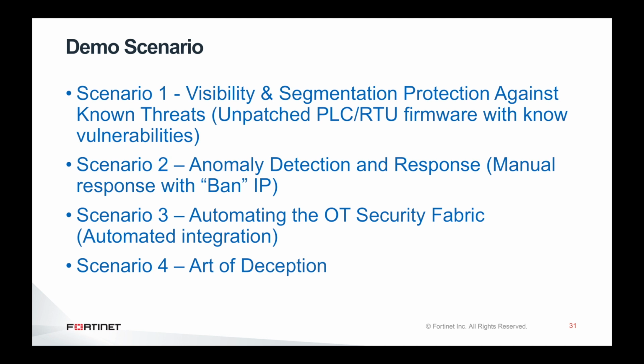Now, the use case here is virtual patching. So what is virtual patching? In most ICS environments, PLC and RTU are running legacy firmware which has known vulnerabilities with CVEs reported against this firmware. As plant managers do not want to disrupt production, these PLC and RTU are usually left unpatched, which exposes them to attack.